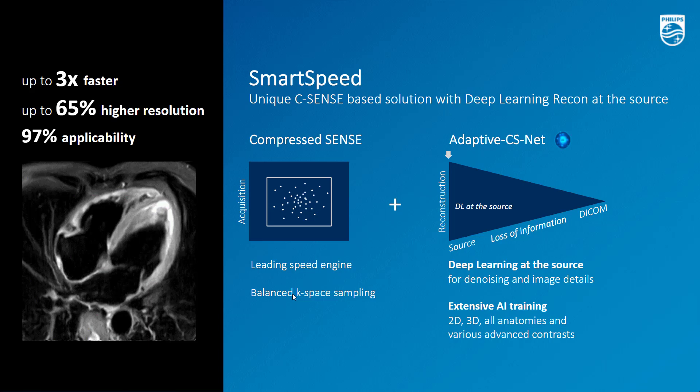How does Smart Speed work? First, Smart Speed is the only AI solution in the industry leveraging the Compressed SENSE speed engine. Compressed SENSE is a proven leading acceleration engine — that's why Smart Speed is so fast. Second, Smart Speed leverages a deep learning reconstruction technology different from other technologies on the market. Smart Speed AI is applied at the source of the signal, where information is the richest, in order to maximize denoising performance while preserving details.